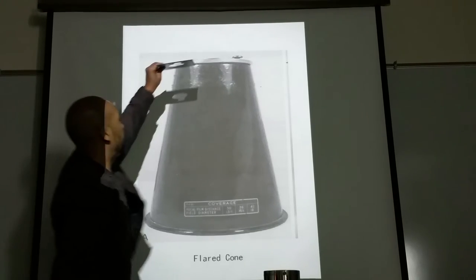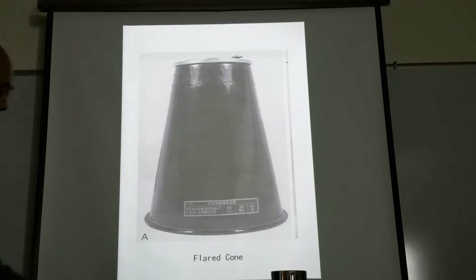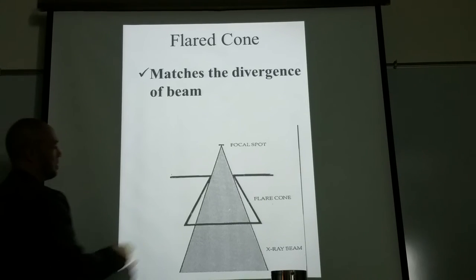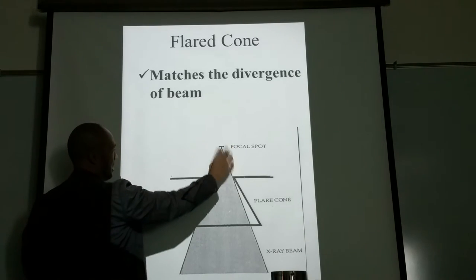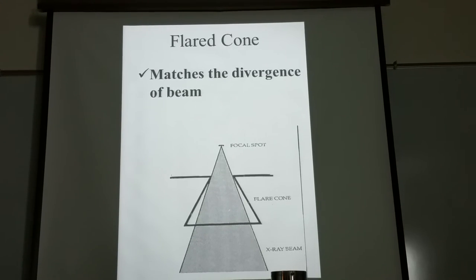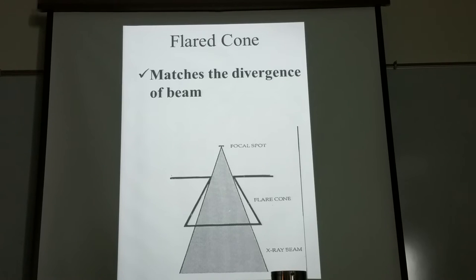The second type is cones — we have the flared cone and the cylindrical cone. The flared cone, like the aperture diaphragm, slides onto the x-ray tube slot. It does match the divergence of the beam, but because it matches the divergence, it isn't effective in cleaning out the penumbra on the edges. We can still control the size of the beam, but it doesn't truly clean out the beam edges.